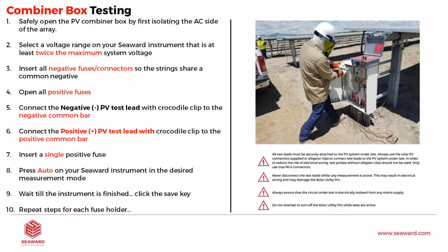Open, close, test, open, close, test, open, close, test. So very quickly, within 10 to 12 minutes, we can test a full combiner box very easily. The only kind of danger here that we're going to face is, and the reason I did ask everyone to take out the fuses from all of the harnesses, if we push 2 or more of those fuses together when we're connected to the common positive and the common negative, those strings are going to be in parallel.